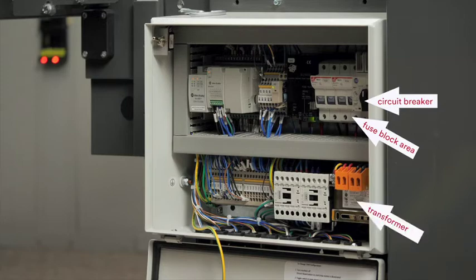The transformer converts the main line 120 AC volts to 24 AC volts required by the DC power supply. The DC power supply converts the 24 AC voltage to 24 volts DC voltage needed to power up the PLC, sensors, solenoids, lights, and control relays.